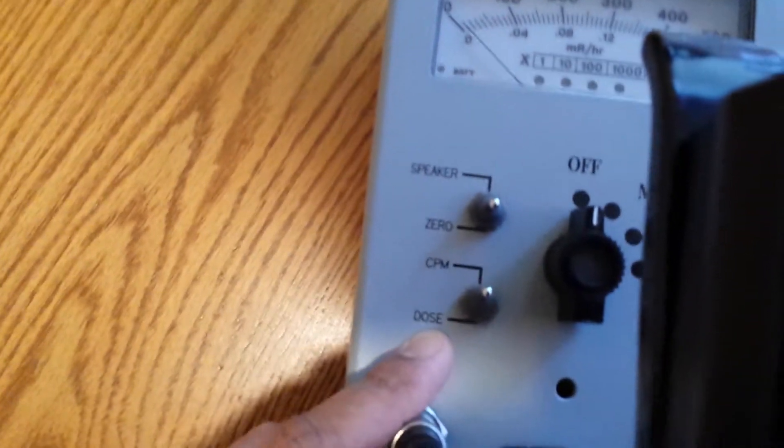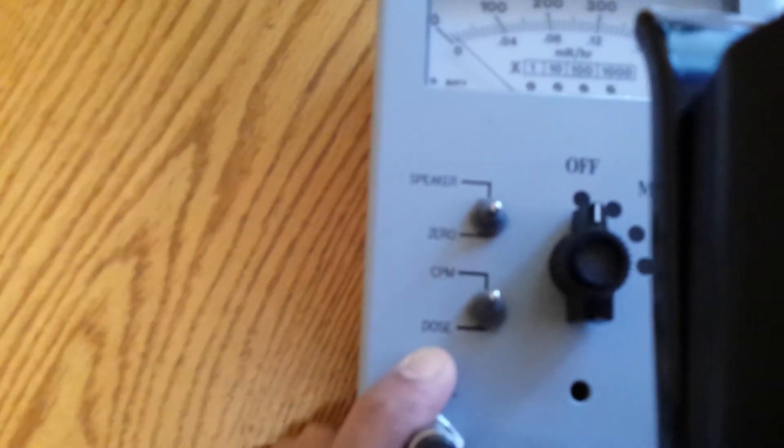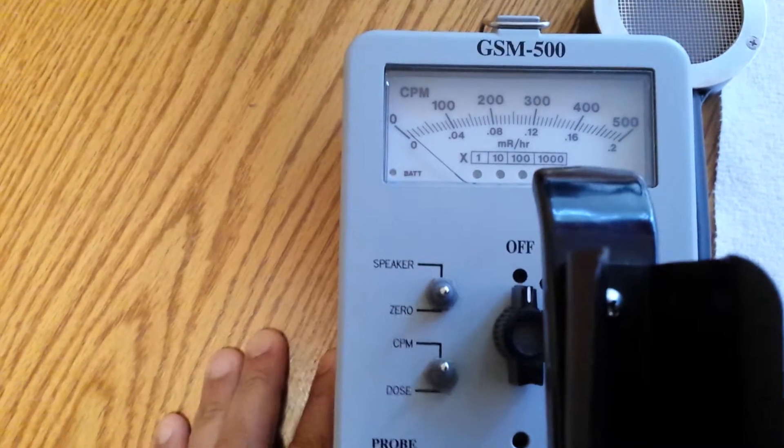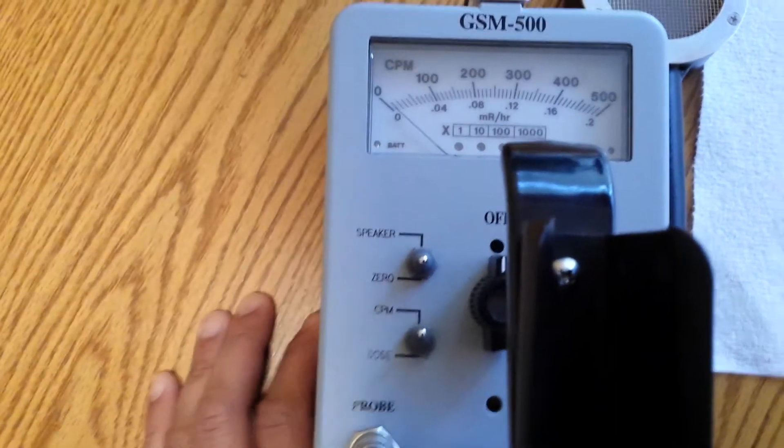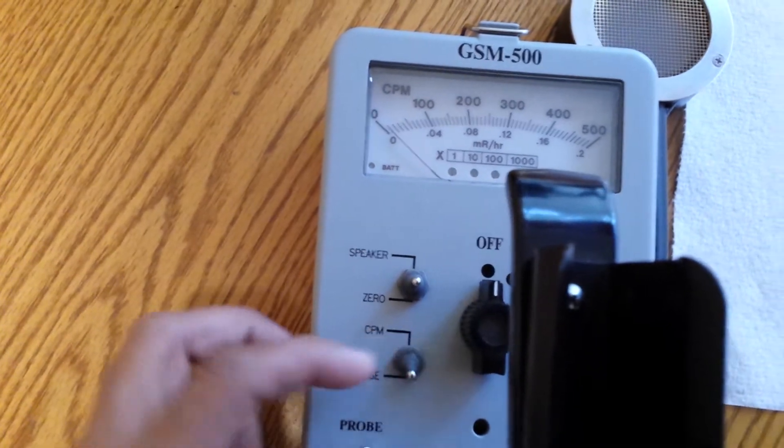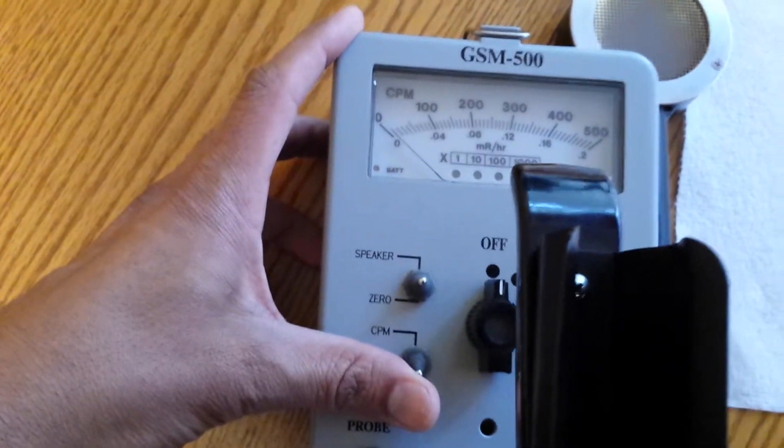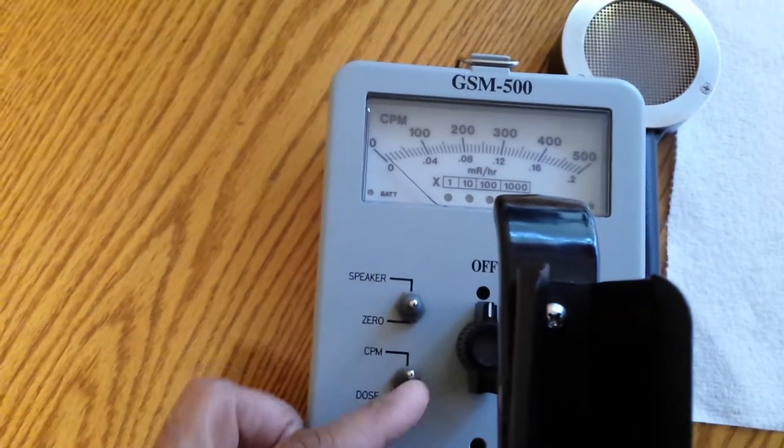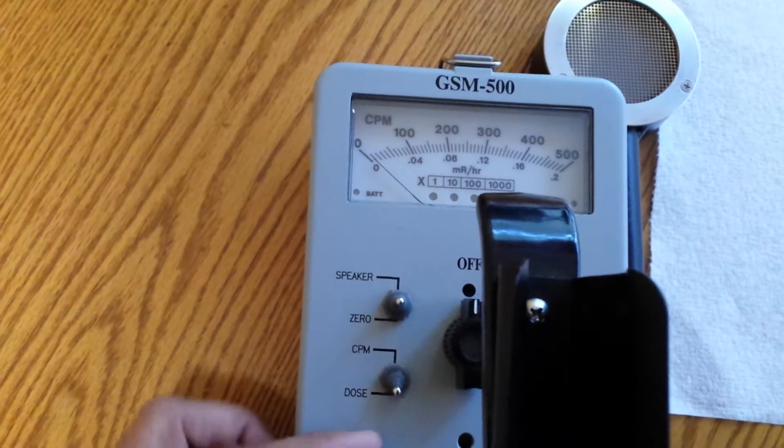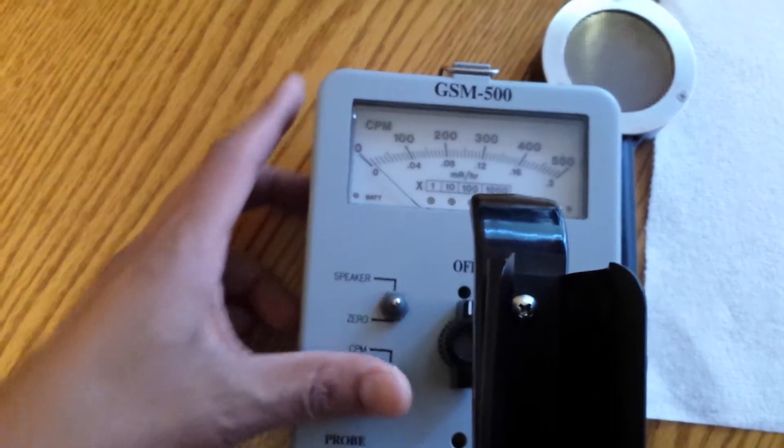Instead of just measuring counts per minute, we'll actually be able to measure the dose because it will be very accurate. This instrument is calibrated with cesium-137 for dose measurement. So this is a pretty neat feature of this instrument. We can flip between counts per minute and dose rate.